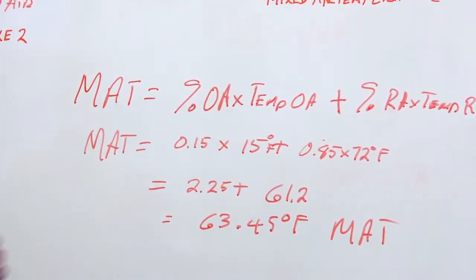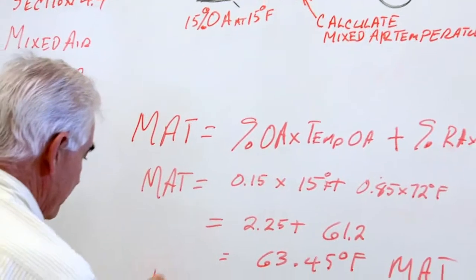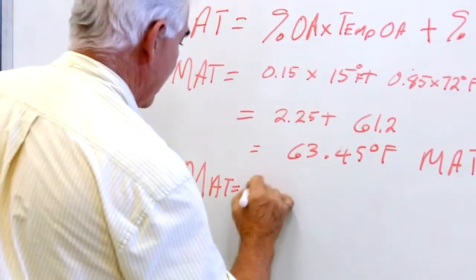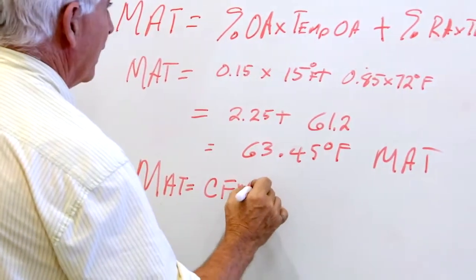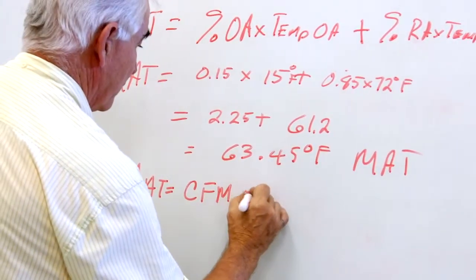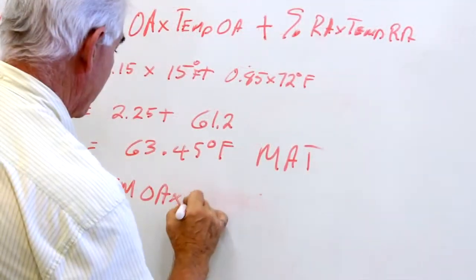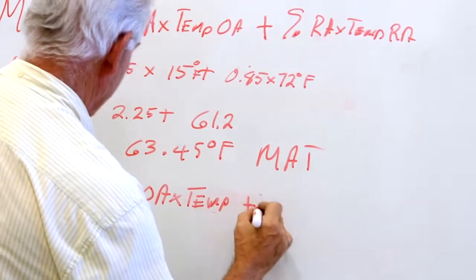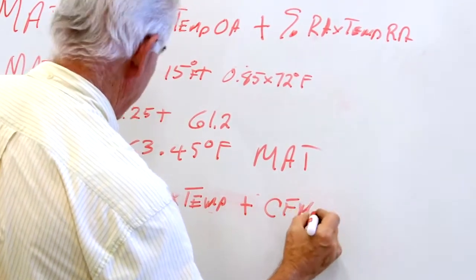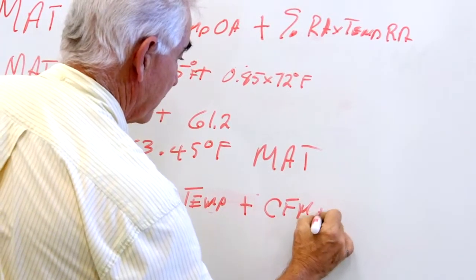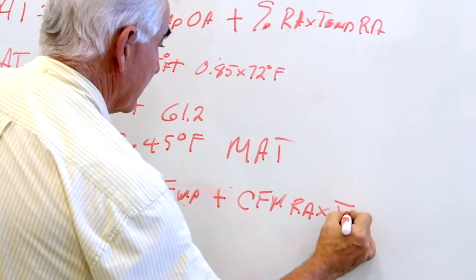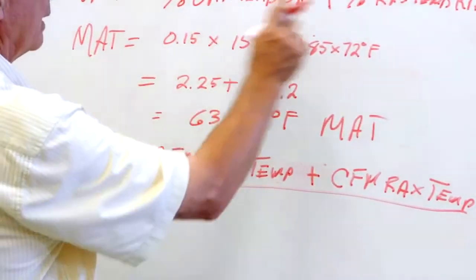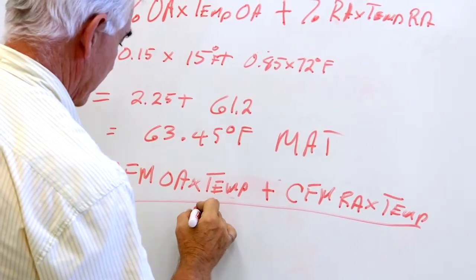The other equation that we might use is the mixed air temperature equals the CFM of outdoor air times the temperature plus the CFM of return air times the temperature, divided by the total mixed air CFM.